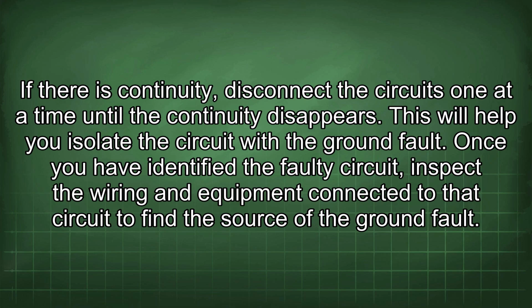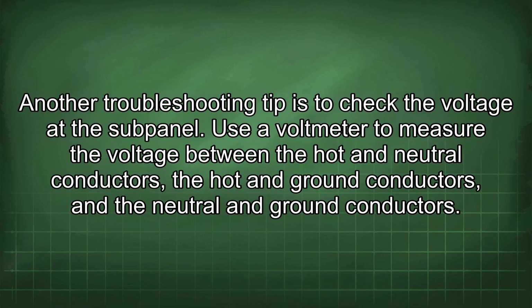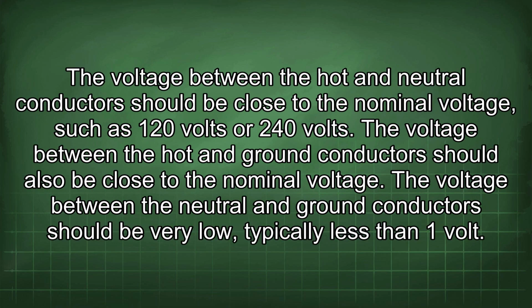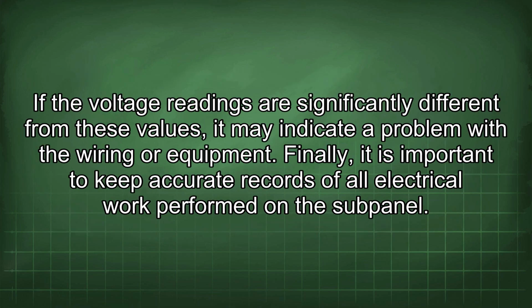Once you have identified the faulty circuit, inspect the wiring and equipment connected to that circuit to find the source of the ground fault. Another troubleshooting tip is to check the voltage at the subpanel. Use a voltmeter to measure the voltage between the hot and neutral conductors, the hot and ground conductors, and the neutral and ground conductors. The voltage between the hot and neutral conductors should be close to the nominal voltage, such as 120 volts or 240 volts. The voltage between the hot and ground conductors should also be close to the nominal voltage. The voltage between the neutral and ground conductors should be very low, typically less than 1 volt. If the voltage readings are significantly different from these values, it may indicate a problem with the wiring or equipment.